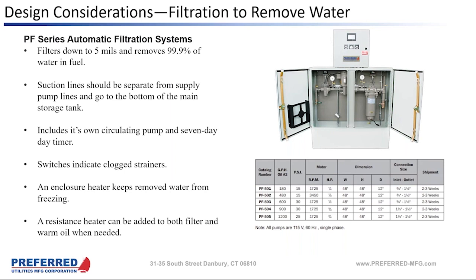The second question that I get all the time when I'm doing startup commissioning on these is how often should we set them up to run? And there's really no hard and fast rule. I think it comes down to the size of the tank and the usage. We mentioned that in our controls we have a 7-day setup where you can set it up to run for X number of hours, starting at a certain time on a certain day of the week. I have run into facilities that over filter their fuel, where they run it 24/7. And you can actually see where you're going to age the fuel prematurely.